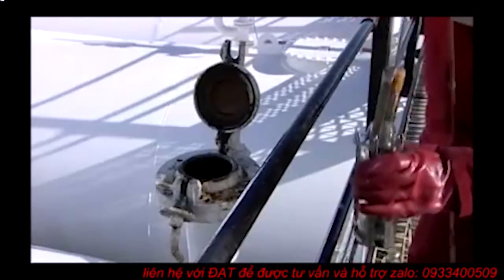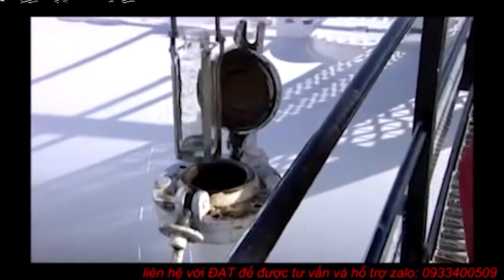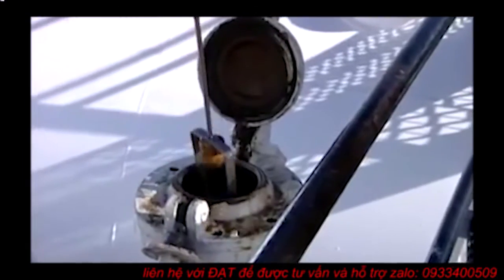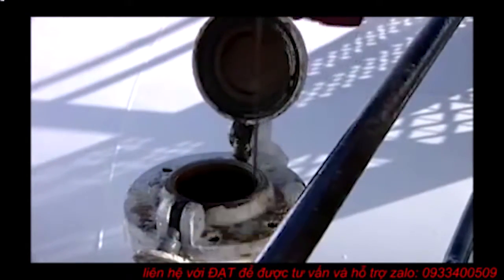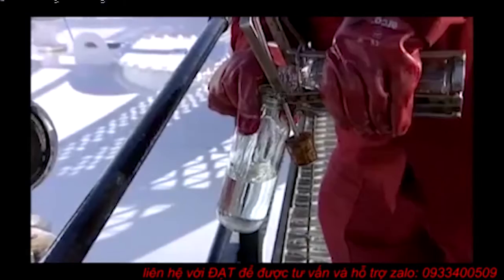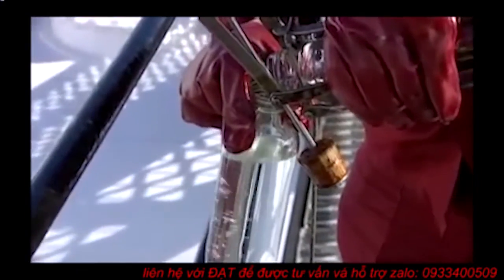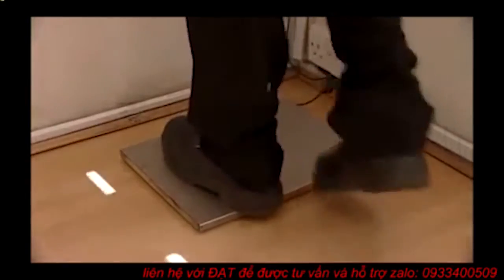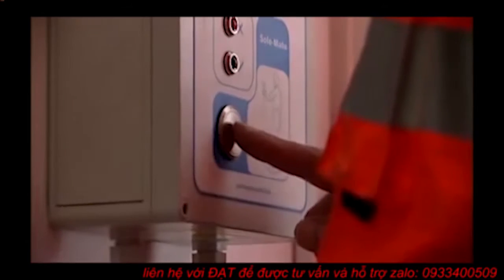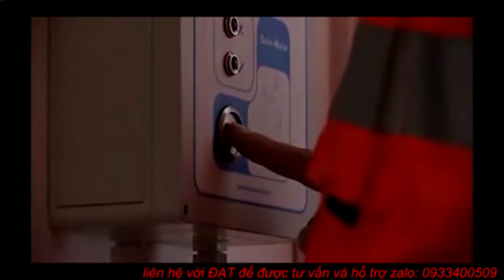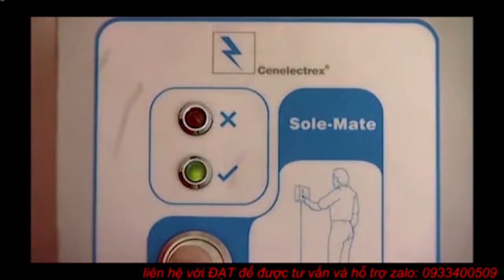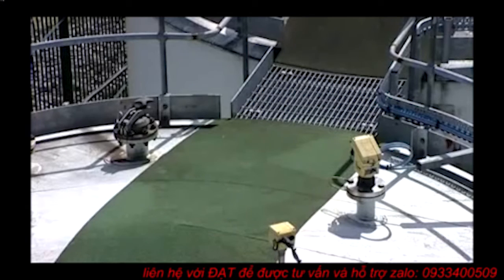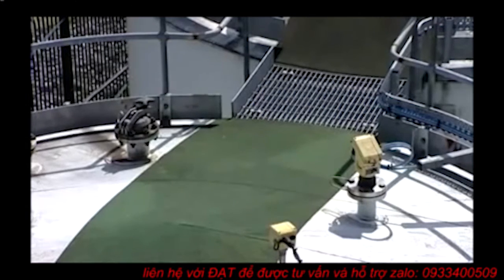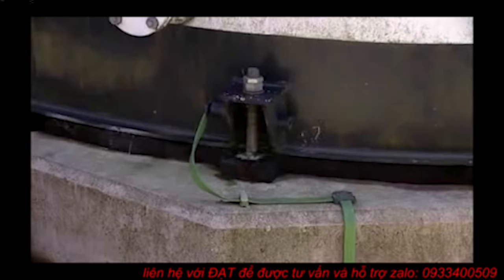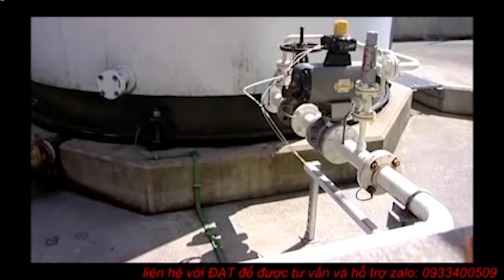The equipment for dipping or sampling should be of conductive material throughout and bonded to the tank, or of natural fiber. Dipping or sampling should only take place after the appropriate relaxation time has elapsed. If flammable liquids are handled, static dissipative footwear should be worn and tested on a regular basis by all people present. The proper installation and effective inspection and maintenance of earthing and bonding systems and devices are important in the protection of personnel and equipment.